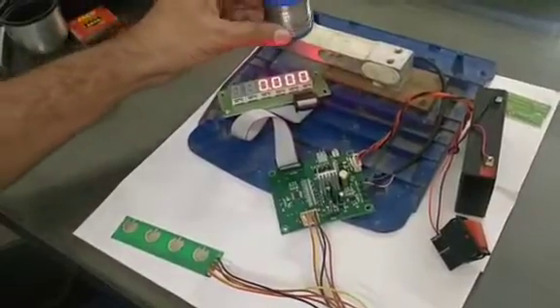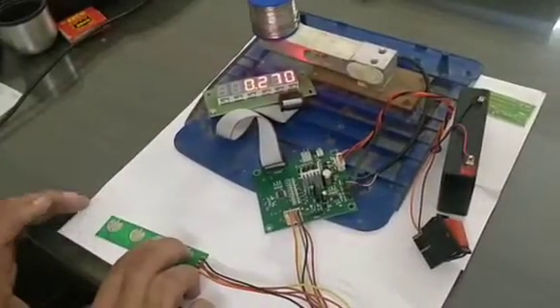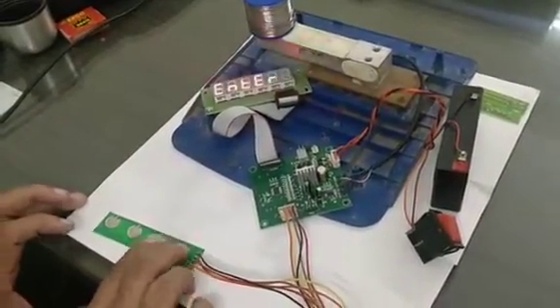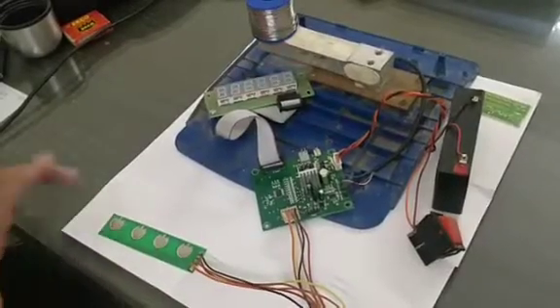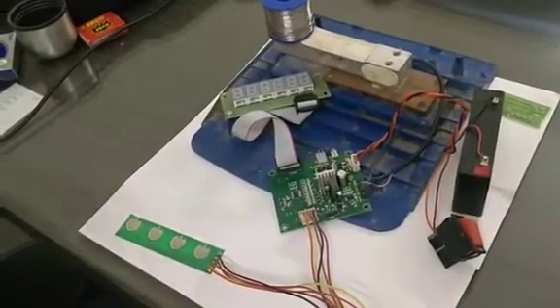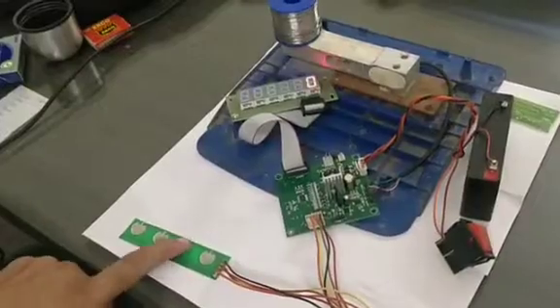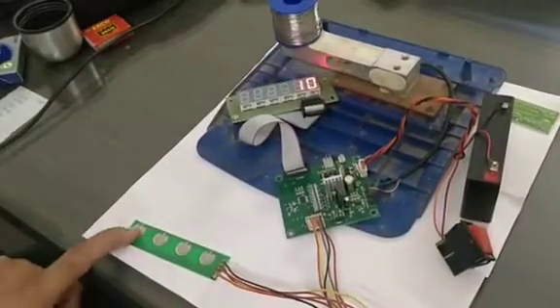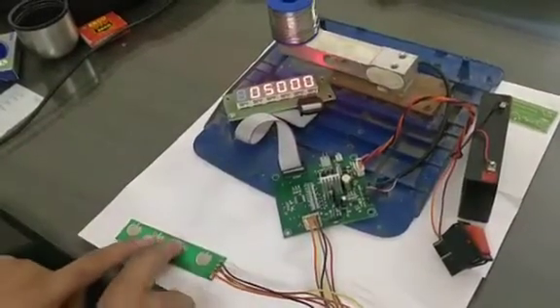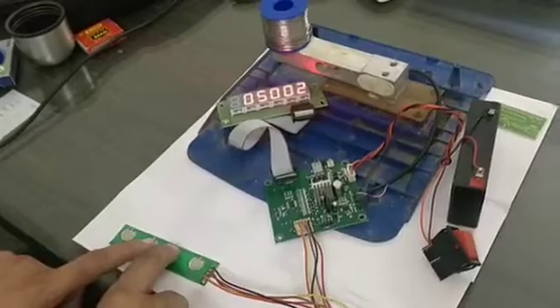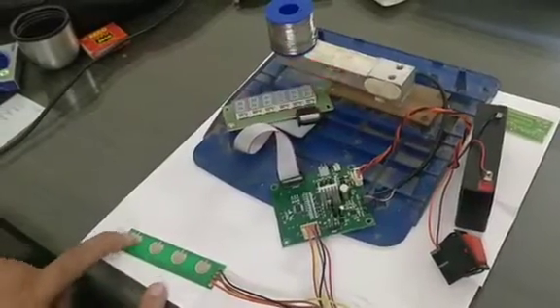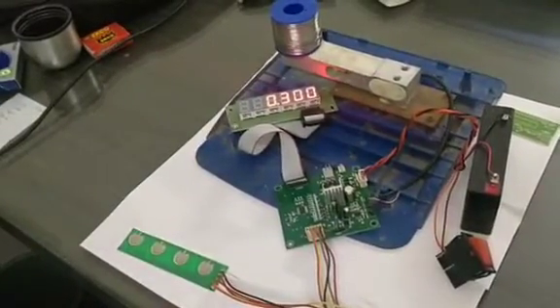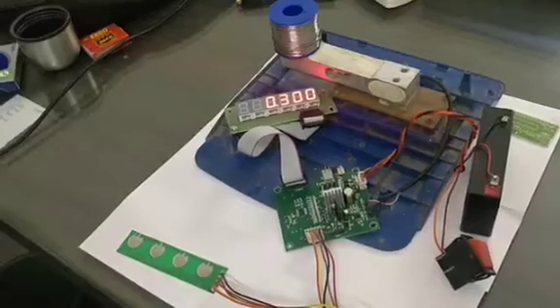I am putting some weight here and then go to calibration mode by pressing key 3 and key 4. This will show enter but it will not go to calibration mode. It will ask the password which is 10. Then it will ask the weight. I say this is 300 grams and now this is complete the calibration mode.